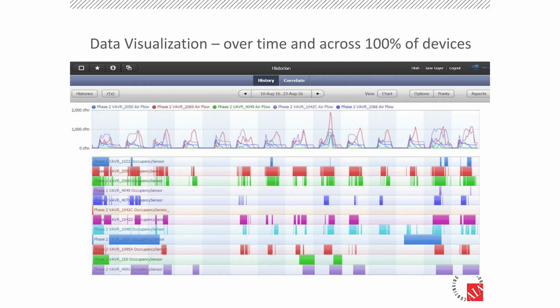And then this is the result, which I think is such a cool visual. Each one of these bars is one of the spaces, and where it's colored, that's when it's occupied. So you can very visually see, well, this is Saturday and Sunday. This is about a 2-week time span. This is Saturday and Sunday. None of these spaces were occupied on Sunday. This is the weekend as well. And then during the week, in the middle of the day, of course, students were in the spaces. But everywhere that's blank, there was energy savings to be had. So that's what we're showing on this top graph, the airflow to the space. In many situations, that airflow is 0 in all of those spaces. We do still maintain temperature in the space, so if someone does come in, it's not 85 degrees or 65 degrees. It's a comfortable temperature, but we're just not delivering ventilation air to the space based on the occupancy sensor.